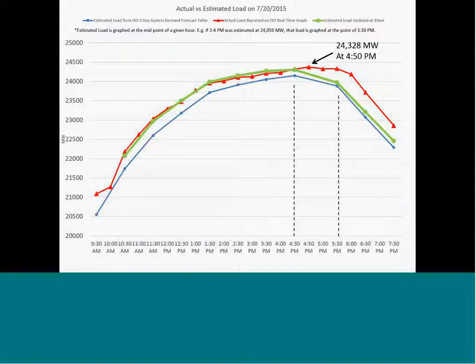One of the things this graph shows us is that as you approach that peak, the curve really flattens off. As we'll hear from some people, starting your load shed an hour or even maybe an hour and a half to 2 hours early can be a good way to be a little cautious, because with the curve flattening out, a change of 500 megawatts here or there could mean the peak could move an hour early or an hour back.